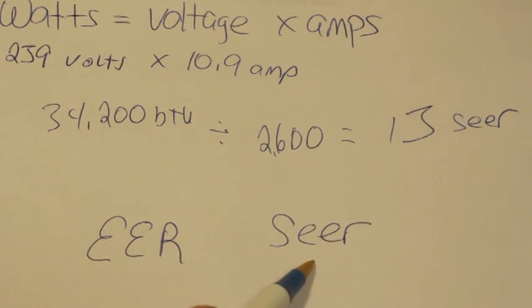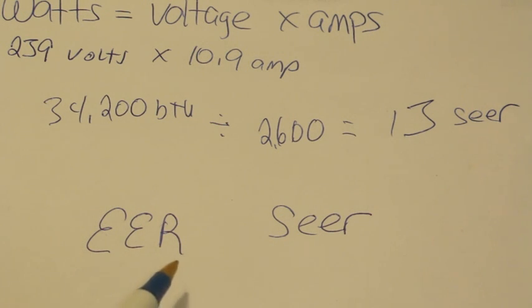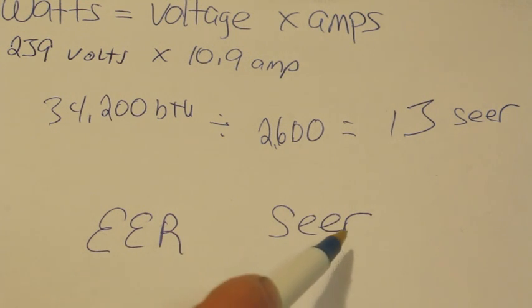Alright, now what SEER rating is, it basically uses this same formula except for the outdoor temperature. It figures it through a wide range of temperatures throughout the season. So this is at one outdoor temperature basically, and this is at multiple outdoor temperatures. Then they just kind of average them. Alright, so that's basically the difference between EER and SEER. This is energy efficiency ratio, and this is the seasonal energy efficiency ratio. Alright, hope that helped clear that up a little bit.